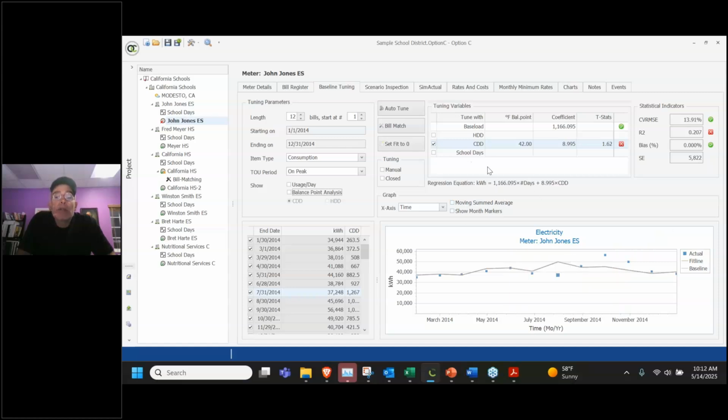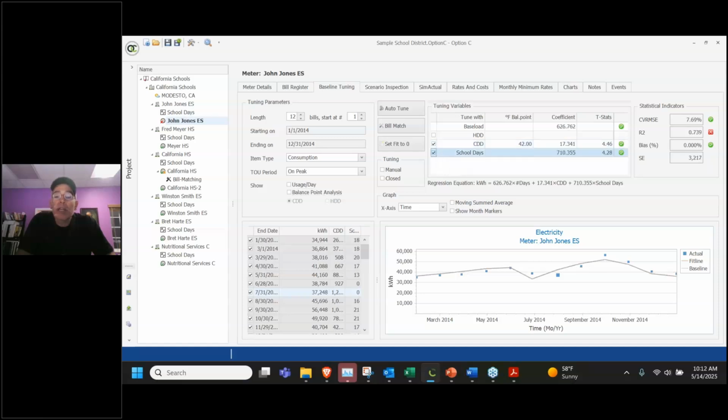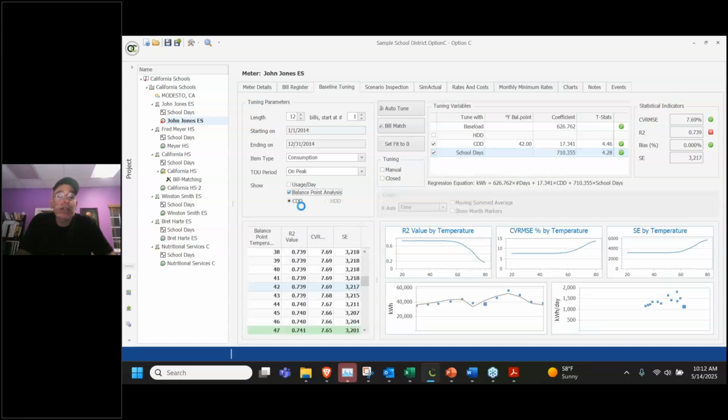So what you could do is, if we had a variable for school days, and I'll show you how to put it in a minute, you can click on this, and now you've got two independent variables. One is cooling degree days and one is school days. And you'll see my fit is a lot better. In fact, I bet I could do even better. I can go back to this balance point analysis and look again, and it says that 48 is the best.